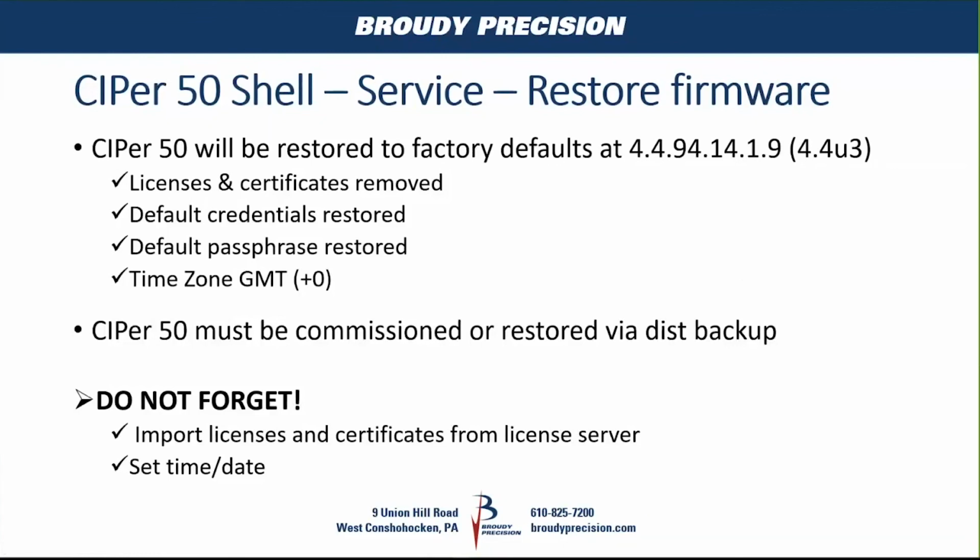So obviously you need to make sure that when you recommission or restore via distribution backup, you must import your licensing and your certificates. Otherwise, when it starts up, it's going to fail right away, and you're going to wonder why, and it's because you don't have a license in there. And you're going to make sure you set the time as well. So if you're doing a commission, one of the steps in there, you can check off to set local time, so it'll do it for you.